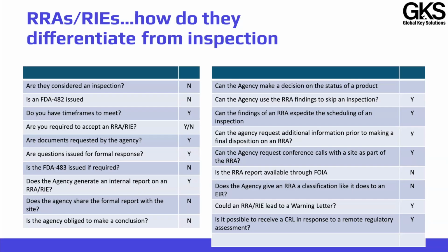Is the FDA 482, meaning the notice of inspection, issued? No, because there's no inspector going into your facility. But it doesn't matter. The FDA continues to gather information from you. Do you have time frames to meet? Absolutely. And this is something that's very important because if you're not able to meet the time frame, you should be able to communicate to the agency and let them know that you need whatever extra time. So keep that in mind. Are you required to accept a remote regulatory assessment or an RIE?